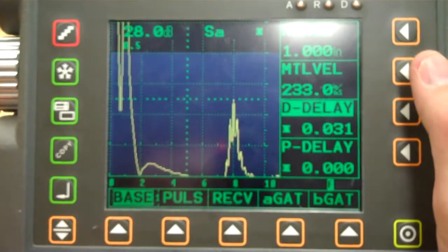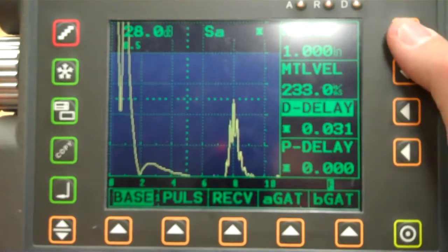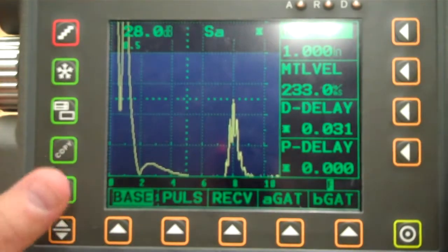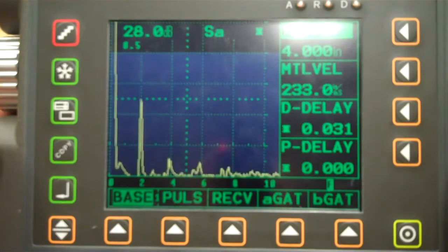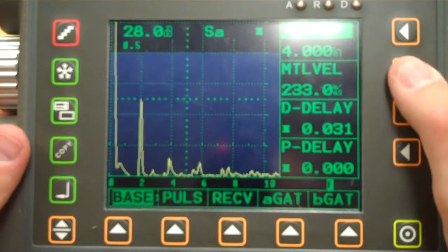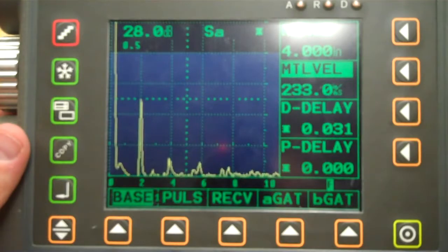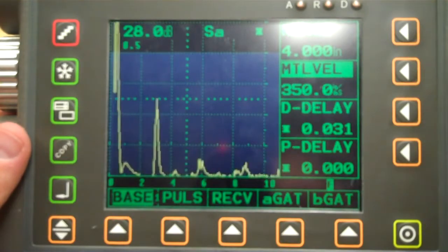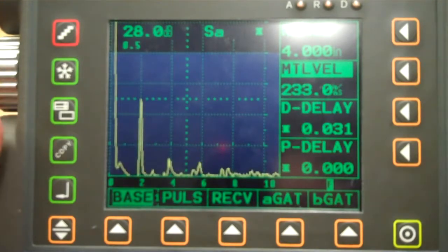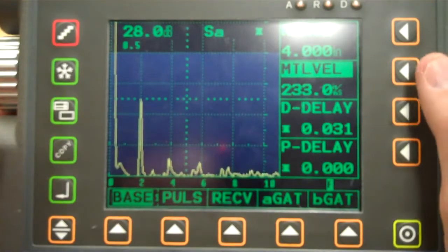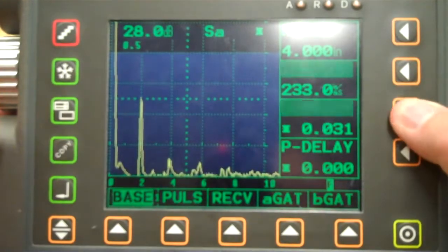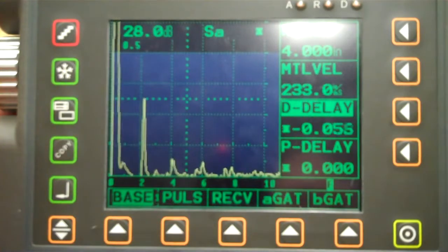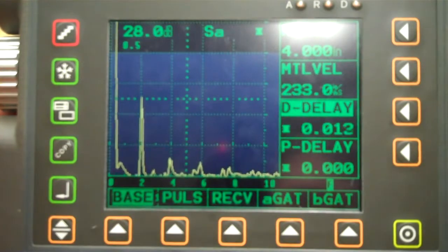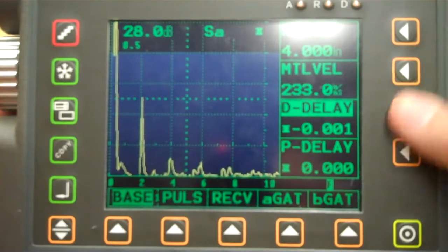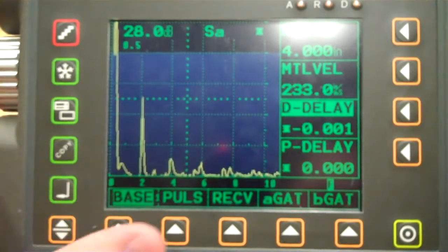So let's kind of calibrate this screen here. Let's say first thing we want to do is go to a 4-inch range. I'm just arbitrarily picking 4 inches for fun. So I'm going 4-inch right there. Then I've got steel, so I would pick my velocity. Okay, and I can just roll through a number of velocities here. 233 or 233,000 inches per second is what we want. That's what that number is. Here's a display delay. I'm going to take that back to 0. Alright, there's a probe delay. I'm going to leave that at 0 right now.